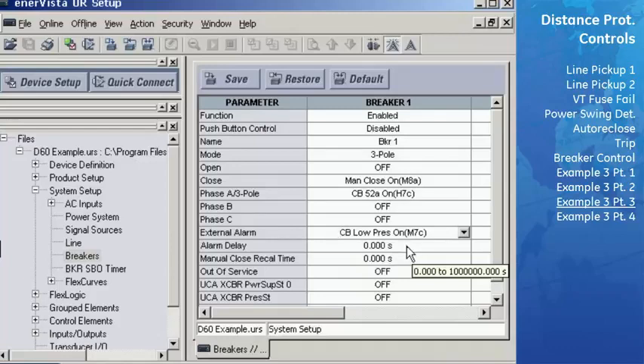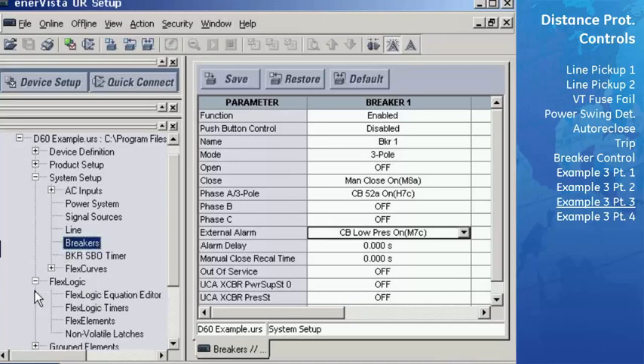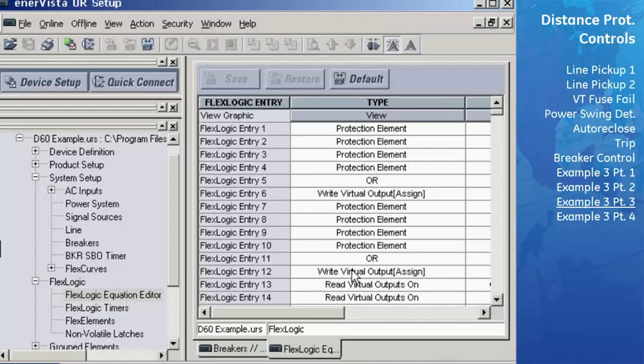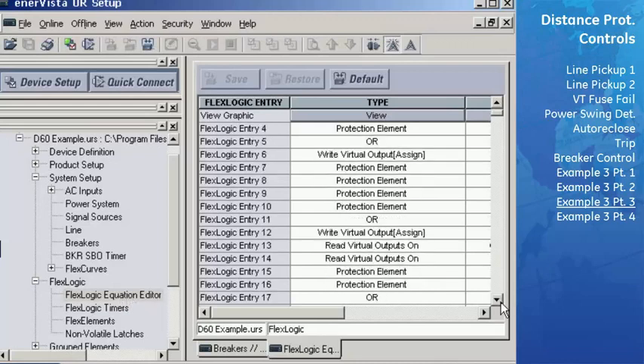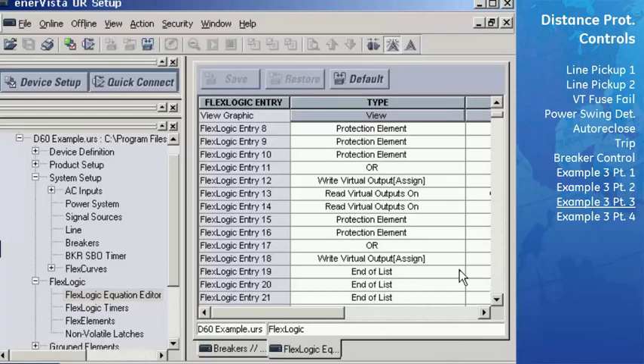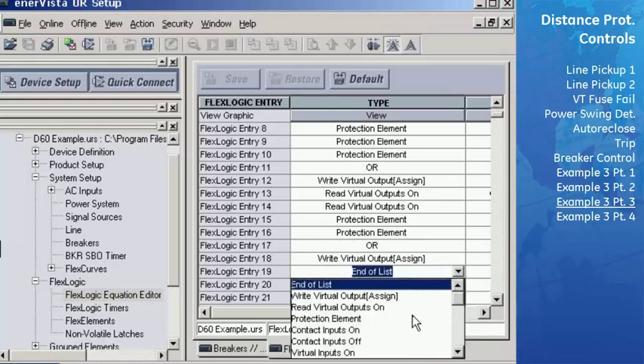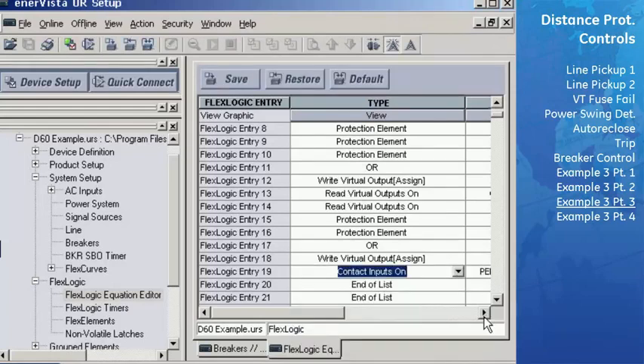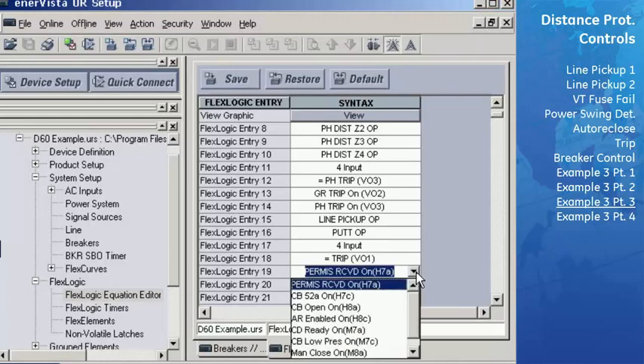When this signal is off, meaning the breaker is not ready, or when a breaker SF6 low pressure alarm is received, the breaker can be considered to be out of service, so we'll have to create this signal in FlexLogic. Open the FlexLogic equation editor under the FlexLogic menu. In the first line of our new equation, select Contact Inputs On and Breaker Low Pressure On in the syntax of the next line.